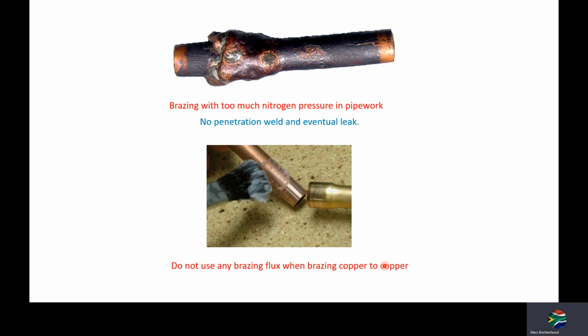Also here too, you must never use any brazing flux when brazing copper to copper. Why? Because there's a high possibility of leakage due to fissures for inexperienced welders. With copper to copper, use a Copper-phos rod, and you want a nice penetration weld. You do not use any flux, unless you're using two dissimilar metals like brass to copper, then you can use silver solder, and then you can use a flux. But you do not use any brazing flux when using copper to copper due to fissures, leakage fissures.